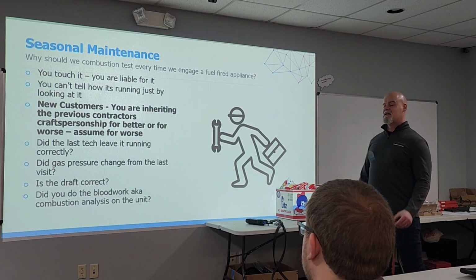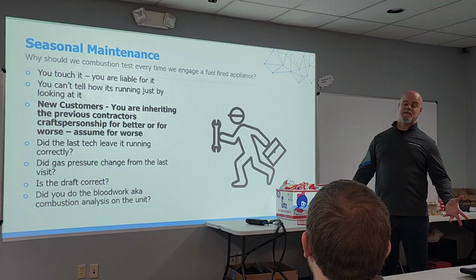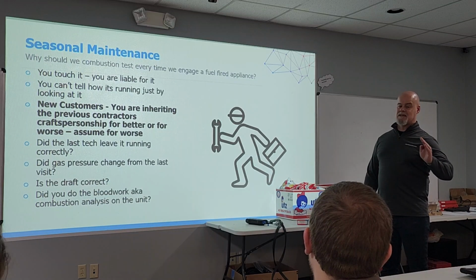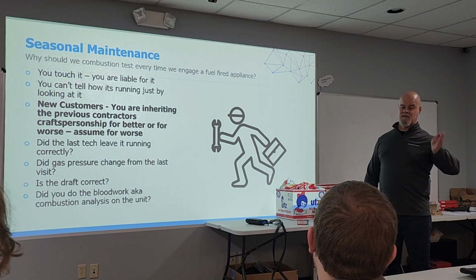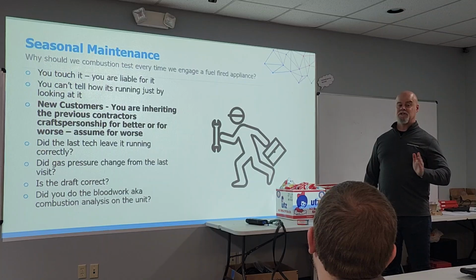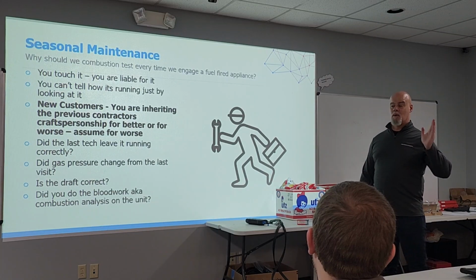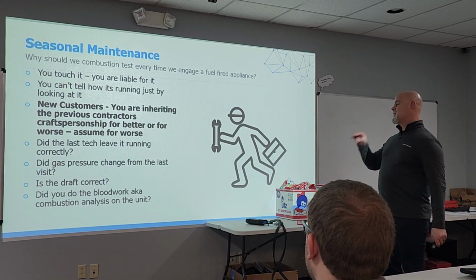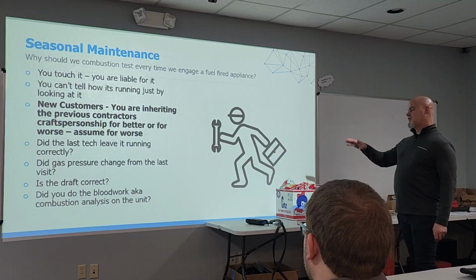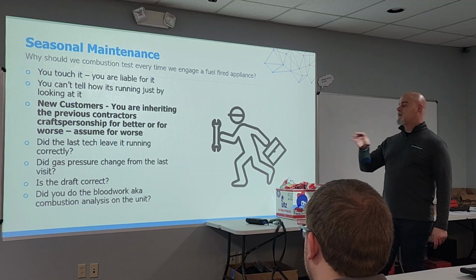We wanna test everything. It's not a conspiracy theory type thing where we gotta test. We're testing because things can change from visit to visit. We are verifying that nothing changed. We're hoping that nothing changed, but we need to verify that with a combustion test. Did the gas pressure change? We gotta verify that. Is the draft correct? Did a bird make a nest in there?